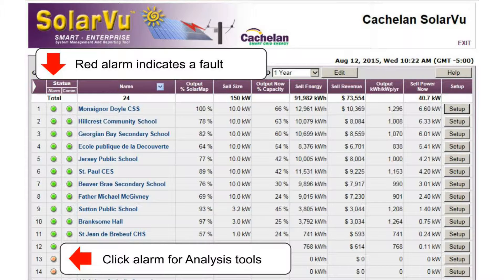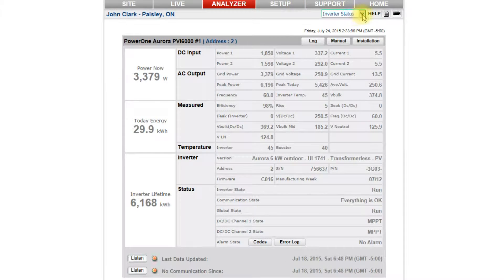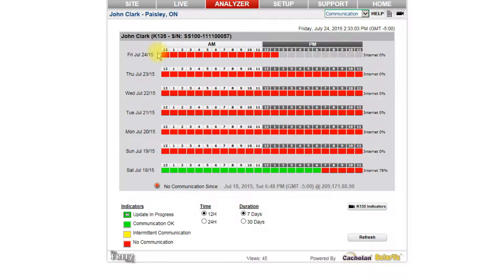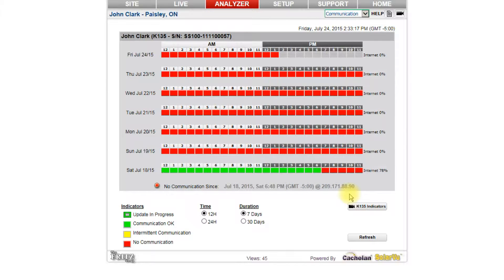Click on the red comms indicator alarm to go to the 30-day communications log to determine the times that the communication is intermittent. This is helpful to determine what to do if the LAN has become disconnected or there is poor 3G cellular reception. Once the problem is fixed, this screen will show within 10 minutes if the connection has been re-established.